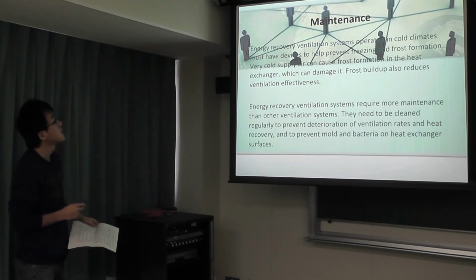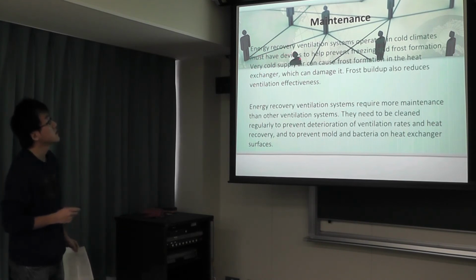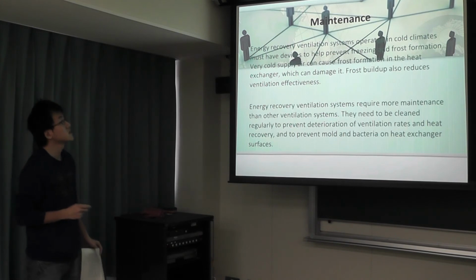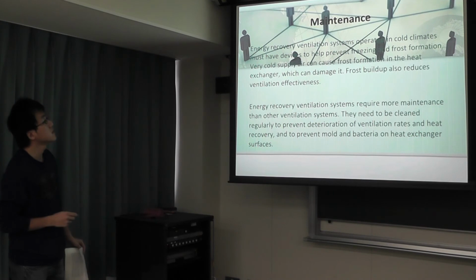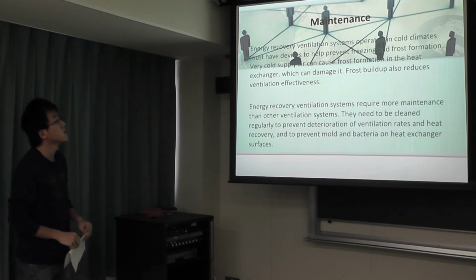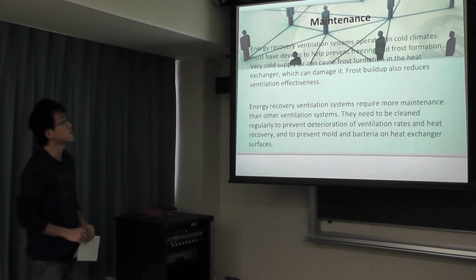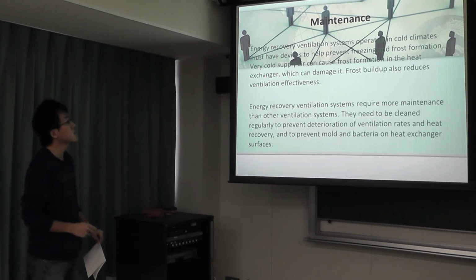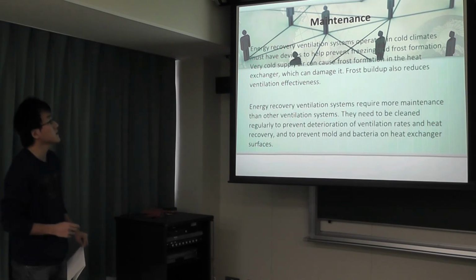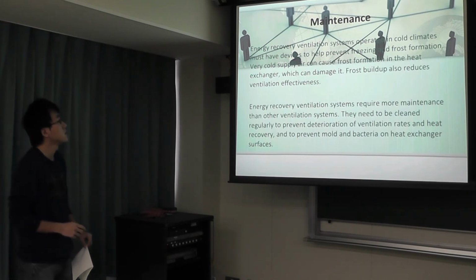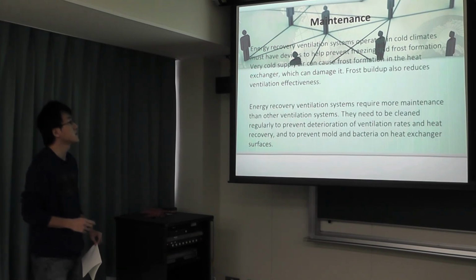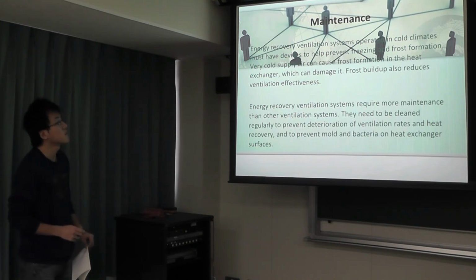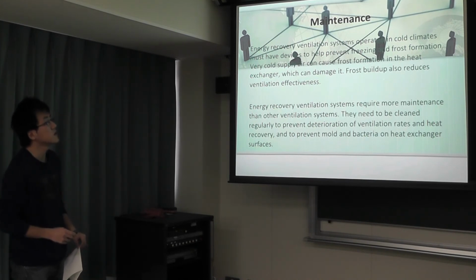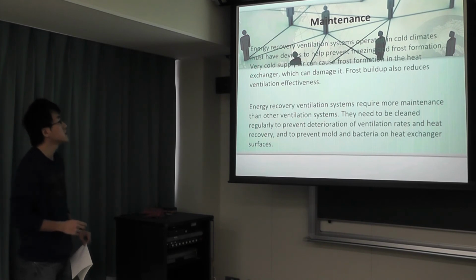Maintenance. Energy recovery ventilation systems operating in cold climates must have devices to help prevent freezing and frost formation. Very cold supply air can cause frost formation in a heat exchanger, which can damage it. Frost build up also reduces ventilation effectiveness.